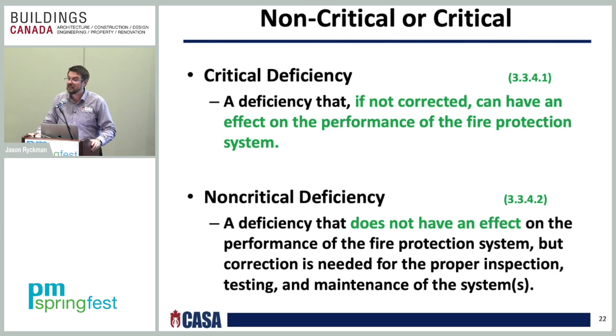You're missing signage on your control valves. Those are examples of non-critical deficiencies. Critical deficiencies, an example would be you have paint on the frame arms of the sprinkler head. Now, if you have paint on the element, that would actually be an impairment. So there's two different degrees there.